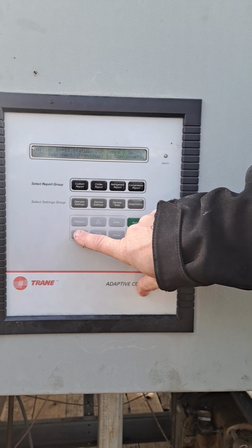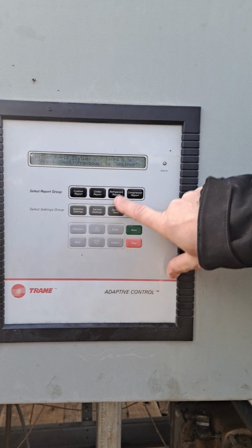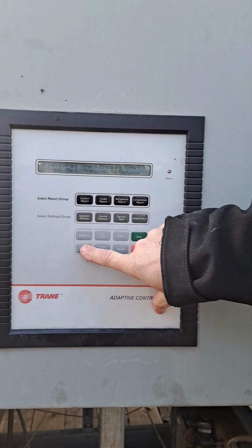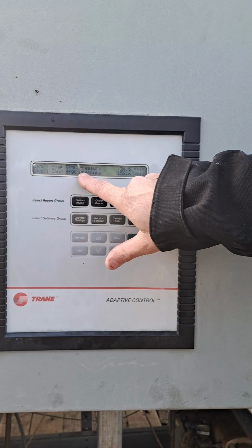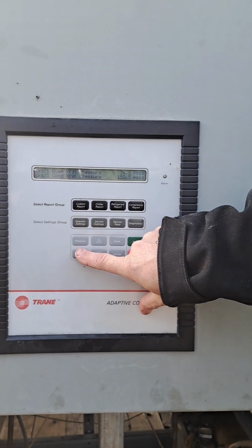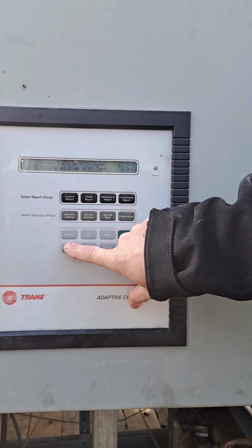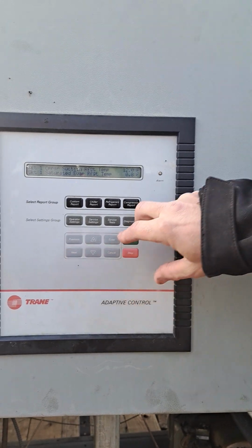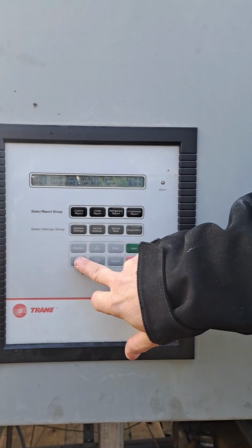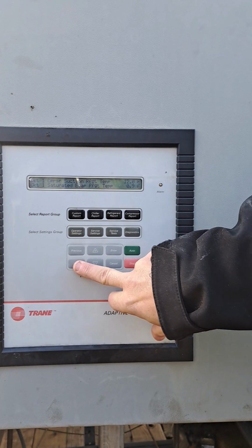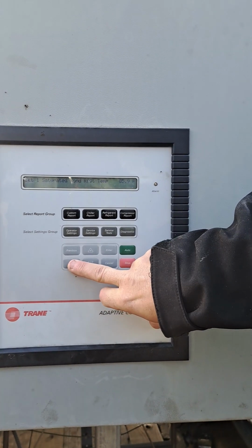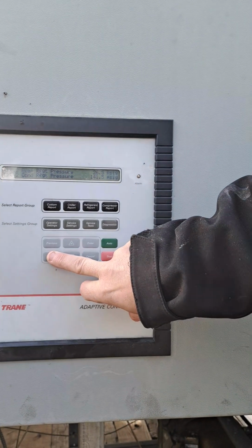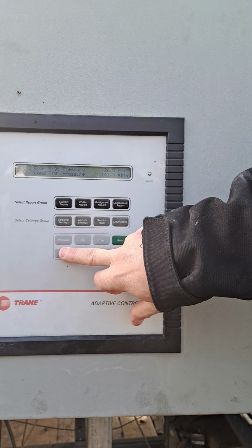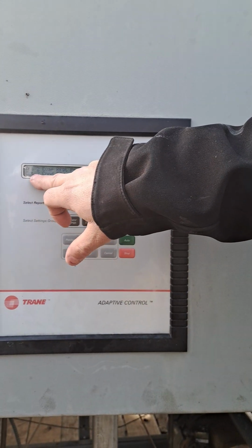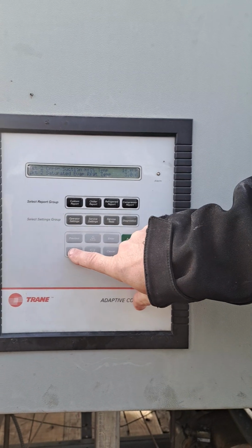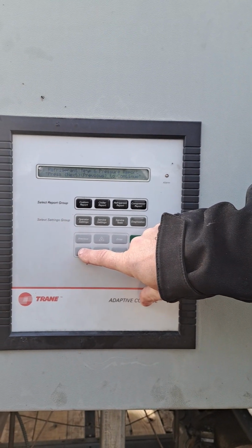Outdoor air temperature is 32. So then you can go to your refrigerant report. So this shows your low side, high side pressures for each circuit. That's your saturated refrigerant temperature. So you're running 0 degrees inside the refrigeration system right now. And this is all the stuff that you're going to log. You're going to go through and it'll show you circuit 1, circuit 2. You want to go through and log all the data for each circuit.